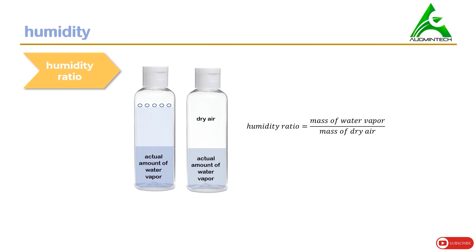To define humidity ratio, we take the ratio of the mass of water vapor to the mass of dry air. An important point to note is that humidity ratio has nothing to do with the maximum amount of water vapor the air can hold. We can write humidity ratio as W = MV / MA. Humidity ratio is denoted as capital W. There is another more complex formula shown just for reference.